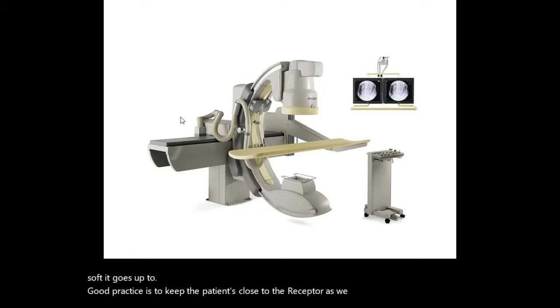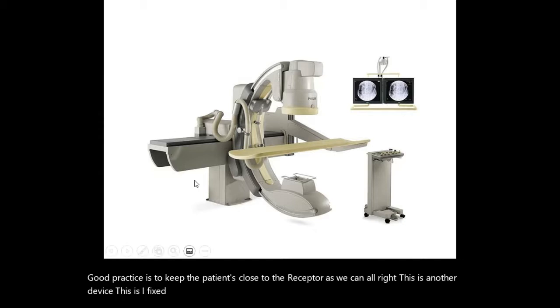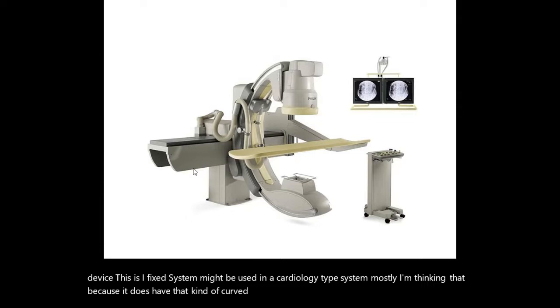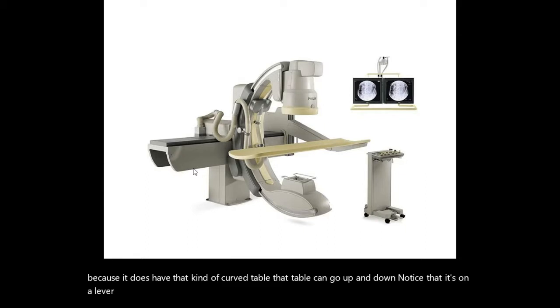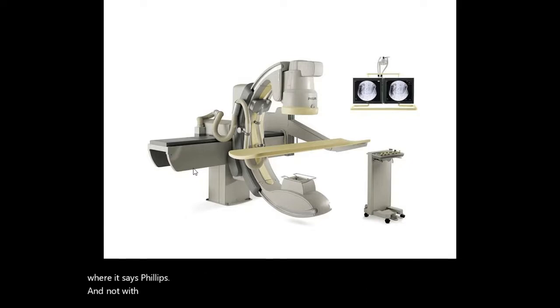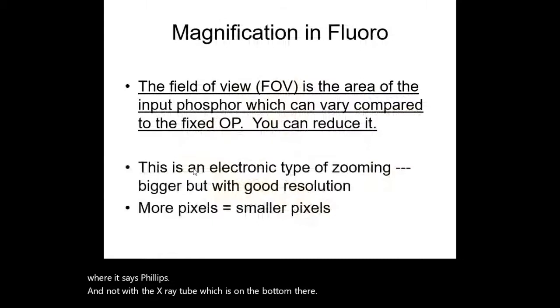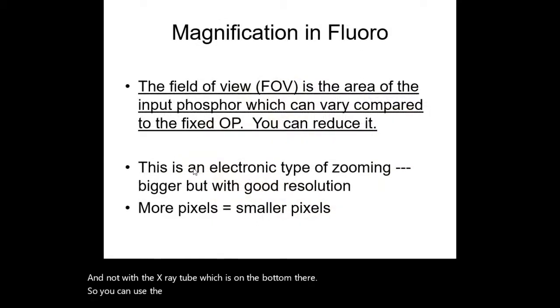All right, this is another device. This is a fixed system, might be used in a cardiology type system, mostly I'm thinking that because it does have that curved table. That table can go up and down. Notice that it's on a lever. So what we would want to do is bring it up as close again to the image intensifier on top, where it says Philips, and not to the X-ray tube, which is on the bottom there. So you can use the geometric principles that you already know to magnify an image in fluoroscopy. That certainly is doable.